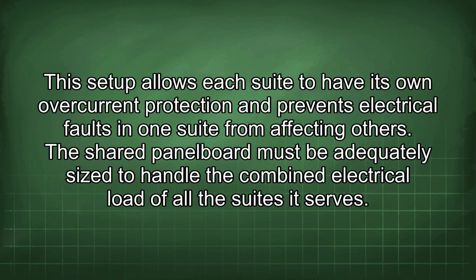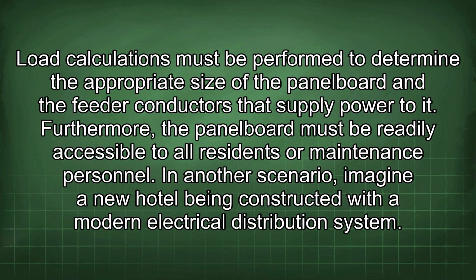This setup allows each suite to have its own overcurrent protection and prevents electrical faults in one suite from affecting others. The shared panel board must be adequately sized to handle the combined electrical load of all the suites it serves. Load calculations must be performed to determine the appropriate size of the panel board and the feeder conductors that supply power to it. Furthermore, the panel board must be readily accessible to all residents or maintenance personnel.